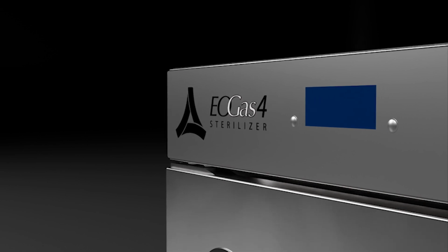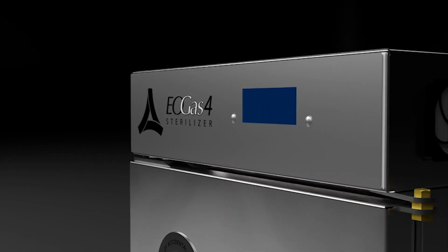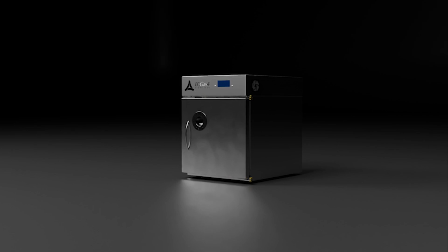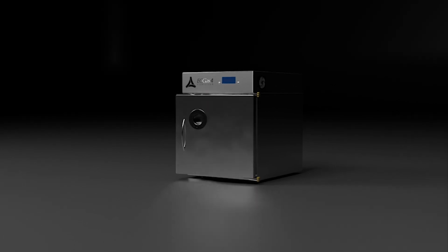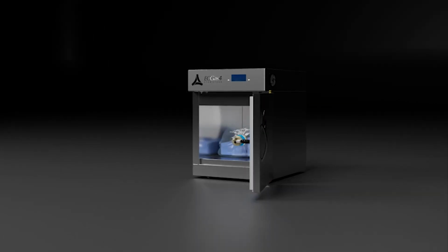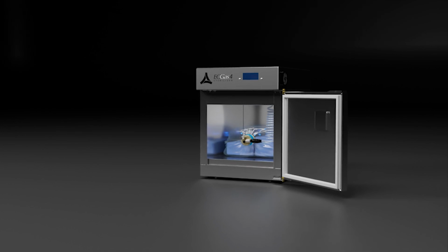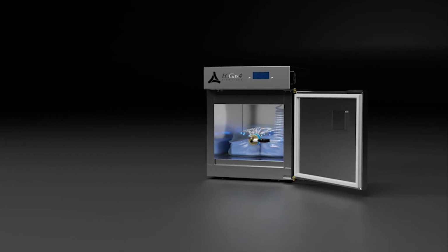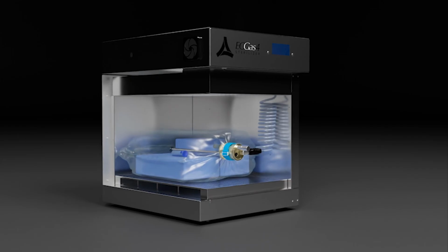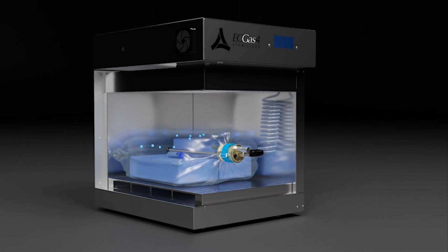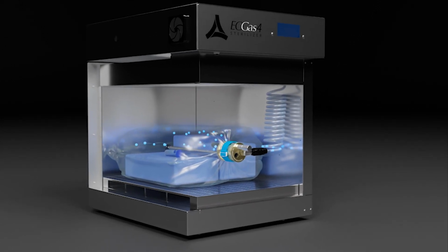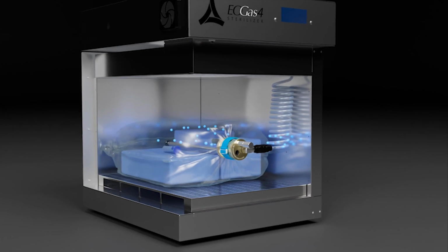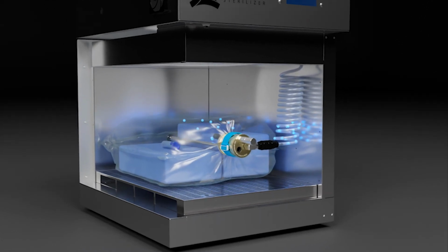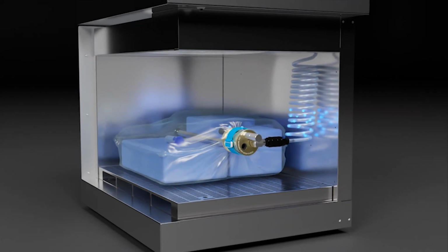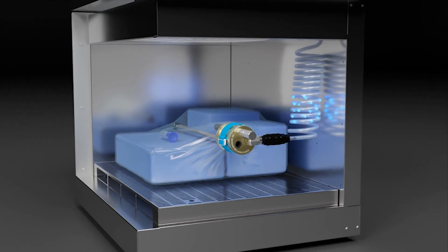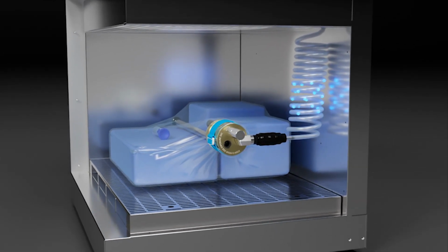How does Andersen's ethylene oxide flexible chamber technology sterilization process work? Ethylene oxide flexible chamber technology is Andersen's proprietary and award-winning sterilization process. It's shared by the Andersen Amproline and EO-Gas 4 models. This cutaway of an Andersen sterilizer reveals a loaded sterilization bag flexible chamber secured with a blue strap around the purge probe. The sterilization cycle begins by purging excess air from the sterilization bag, the flexible chamber.